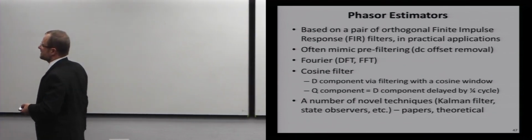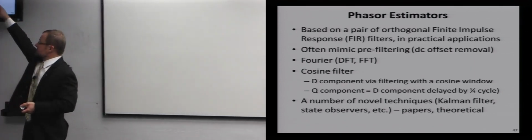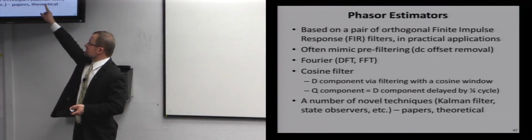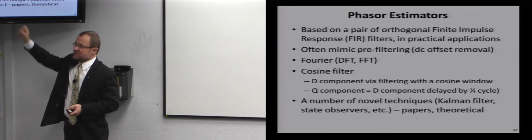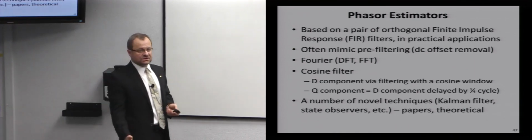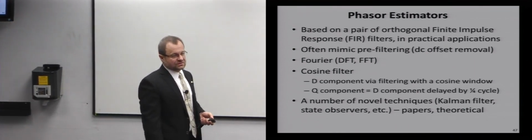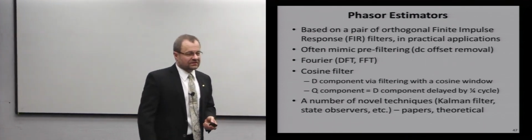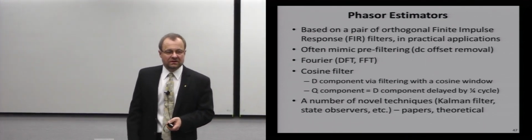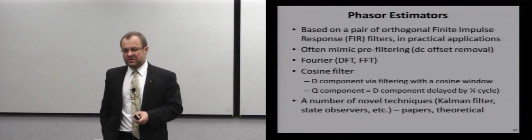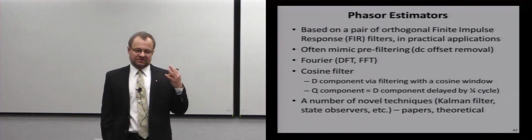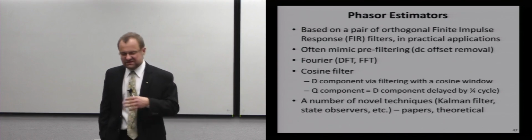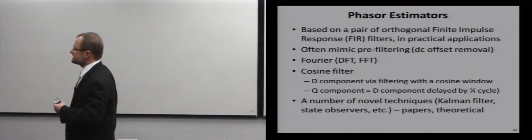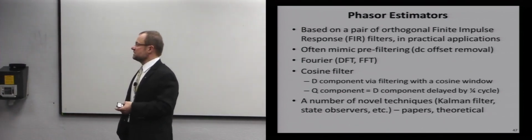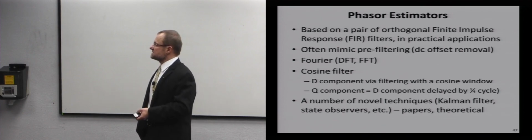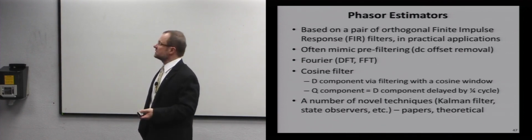So using a cosine to get the direct component and using quarter of a cycle delay to get the quadrature component, that's a very good solution. It works as well as Fourier, but it requires only half of the horsepower compared with Fourier. People wrote tons of papers on Kalman filters and state observers, and it's just a fancy way to get information out of polluted signal. There is no big gain in doing it one way or the other.